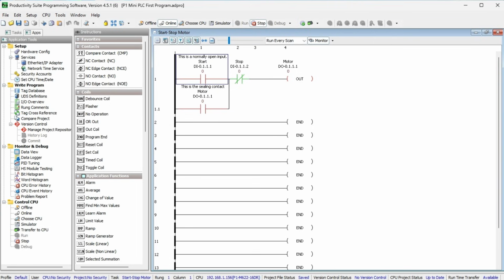The monitoring mode on the ladder editor offers two display modes. The default shows the coils with green, ON, or red, off, line color. This may be preferable when programming and troubleshooting on a desktop. The other monitoring mode is called block fill. This will reflect the states of your logic with green, on, fill, or red, off line color for your contacts and coils. It will make viewing the states of your logic much easier on plant floors and when monitoring the logic from a distance. Call up the Options menu by selecting Tools, Options, Ladder tab from the main menu.